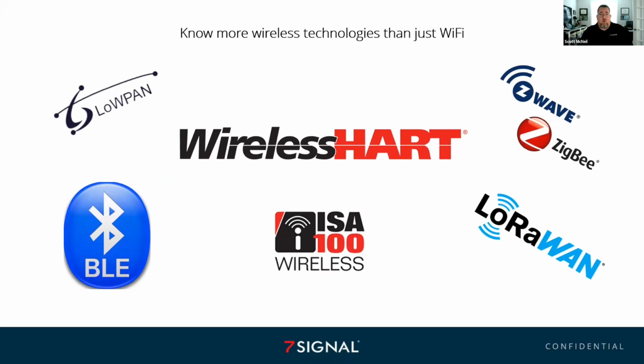Am I saying you have to go in and know all the specific ins and outs? No, but you need to understand the basics, number one, of what WirelessHART uses. As we talked about in the trivia question, what modulation is it using? You need to be able to recognize that modulation. Same with ISA100. You need to understand that these protocols are capable of 128-bit AES encryption, because that's part of the 802.15.4 standard. But there's a ton of stuff on top of that on how it handles the data that's going to be completely foreign as compared to 802.11 in general. So there's really a lot going on with that.